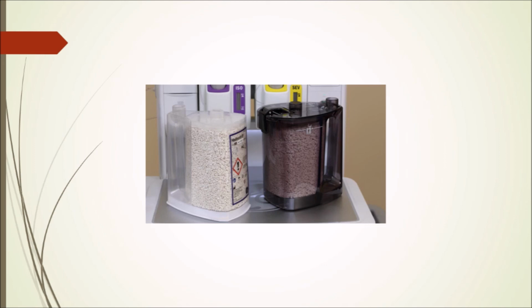The setup is located so as to be visible to the anesthesia provider because visual inspection of its status and operation is very important. At expiration, the expired volume travels through an absorber canister and is exposed to the absorbent granules, where the carbon dioxide is converted to carbonic acid and then to carbonate, water, and heat. So, actually, it's a simple neutralization of an acid by a base.